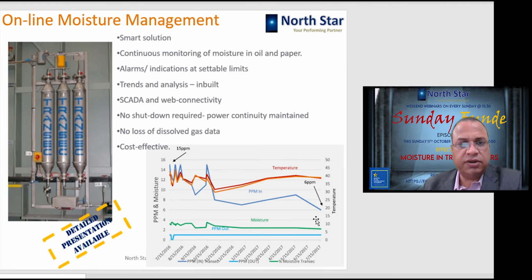It is a very cost effective solution, and this system is also not contributing to loss of dissolved gas data, and for that no shutdown is required. Power continuity is maintained, and while your transformer is working, this machine keeps on sucking the moisture from your transformers.